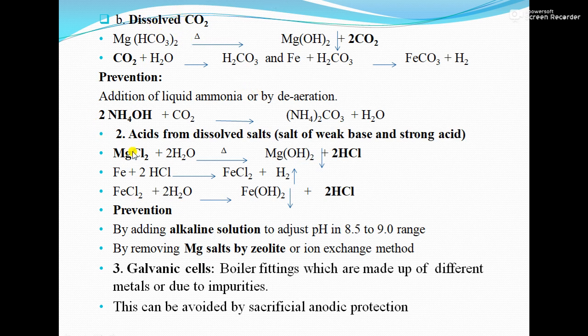Next is corrosion from acid produced by dissolved salts — salts of a weak base and strong acid. For example, magnesium chloride (MgCl₂): on heating, MgCl₂ converts into magnesium hydroxide and two molecules of hydrochloric acid (HCl). This HCl reacts with the boiler metal (Fe) to form ferrous chloride and hydrogen gas. That ferrous chloride reacts again with water giving ferrous hydroxide and two molecules of HCl, which again attacks the Fe metal — so the reaction continues because HCl regenerates.